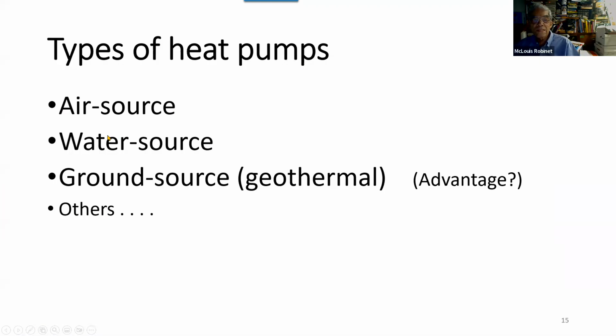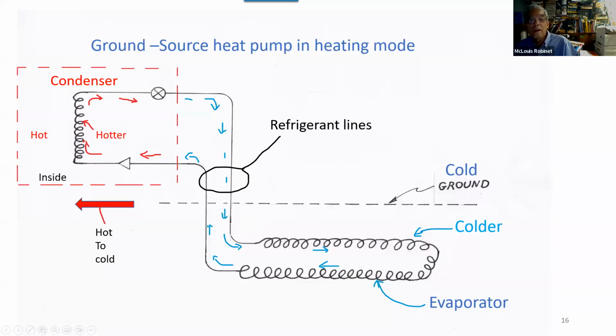Okay, let's look at a ground source heat pump. We still have the basic components, the condenser. Let's say we put the evaporator underground. So here's the evaporator. We would be taking advantage of the constant temperature of the ground. We'd have refrigerant lines going in. But this is a terrible idea.